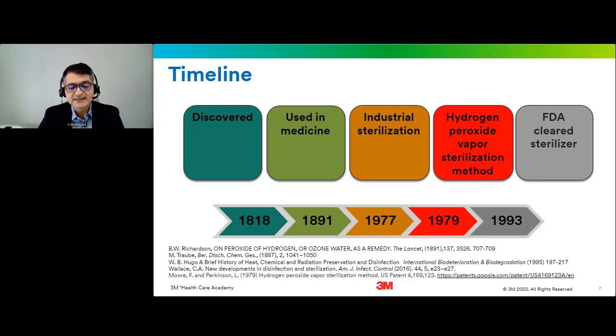While hydrogen peroxide is new to terminal sterilization, it has a long history in the healthcare industry. Hydrogen peroxide was discovered in 1818 by Louis Thenard with a reaction of barium peroxide with nitric acid. Since then, hydrogen peroxide has been used as an oxidizing agent. It was used in medicine in 1891. The initial use of hydrogen peroxide in industrial sterilization may be traced back to 1979 when a US patent was granted to Francis Moore and Leon Perkinson for their hydrogen peroxide vapor sterilization method, which describes it as a cold sterilization process. ASP's first vaporized hydrogen peroxide gas plasma sterilizer, the Sterad 100 system, received FDA clearance in 1993.